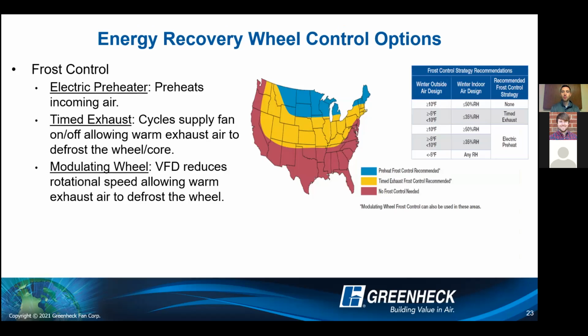So some energy recovery wheel control options. I want to first touch on frost control. So a couple different options that you can have. First one is going to be the electric preheater. So this basically, it is what it says. It preheats the incoming air with an electric heater so that we avoid any sort of cold air moving across that wheel and freezing that wheel. Timed exhaust, really what it does is it cycles the supply fan on and off, which allows, as the wheel is rotating, that warm exhaust air to melt any sort of frost condition that there is.